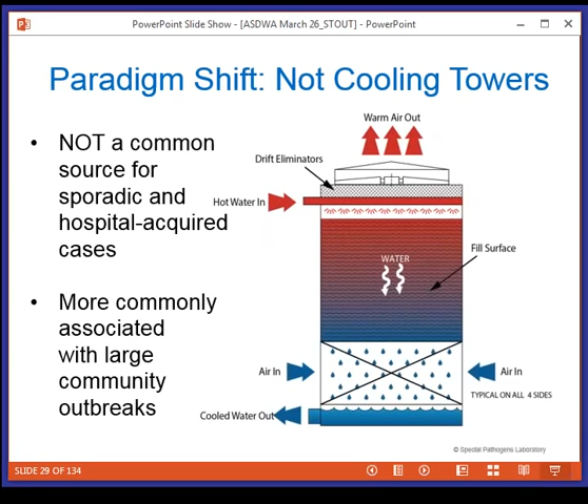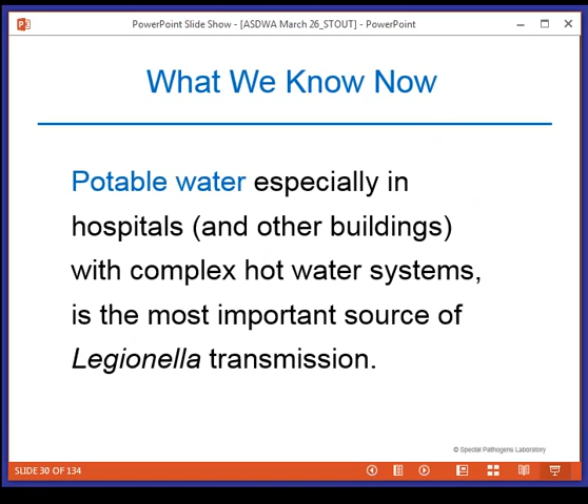Cooling towers are not a common source for sporadic or hospital-acquired cases, but can be and are associated with large outbreaks. So cooling towers aren't off the hook, but the emphasis is on water distribution systems. What we know now is that potable water, particularly the warm water, in hospitals and other buildings is the most important source of Legionella transmission. That's one of the important takeaways.